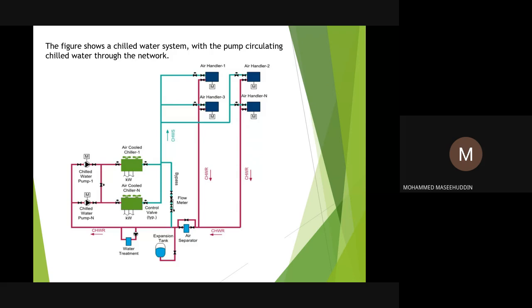So the dosing unit has a sensor on which we specify what kind of conductivity we are looking for in the water. The moment the conductivity of the water goes above that point, this dosing unit starts automatically and pumps the chemicals into the pipes, so that the water gets purified again and goes back to the chiller and through the pump. So this circuit continues. That is the reason the dosing units are used, since it's a closed loop and there will be a lot of contamination inside the chill water piping itself.